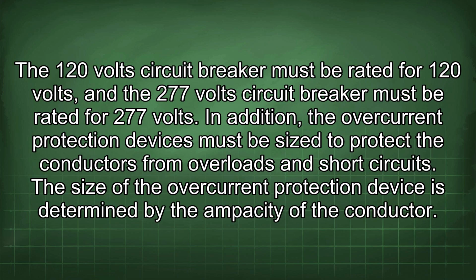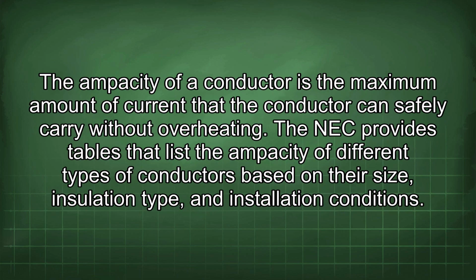The 120-volt circuit breaker must be rated for 120 volts, and the 277-volt circuit breaker must be rated for 277 volts. In addition, the overcurrent protection devices must be sized to protect the conductors from overloads and short circuits. The size of the overcurrent protection device is determined by the ampacity of the conductor. The ampacity of a conductor is the maximum amount of current that the conductor can safely carry without overheating.